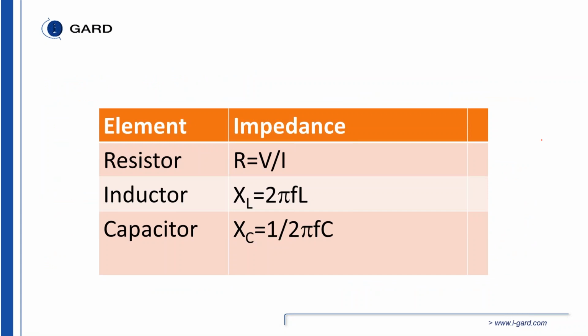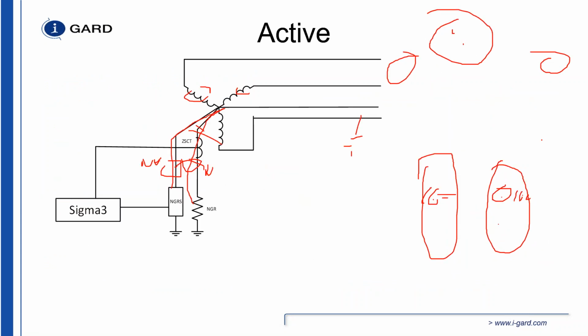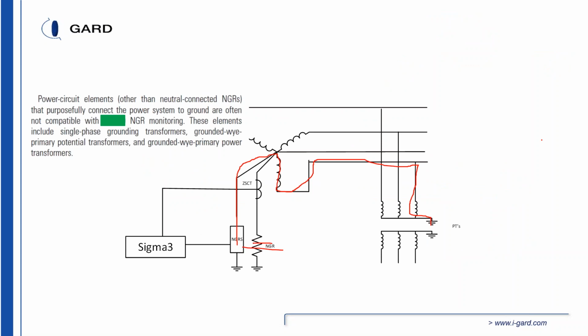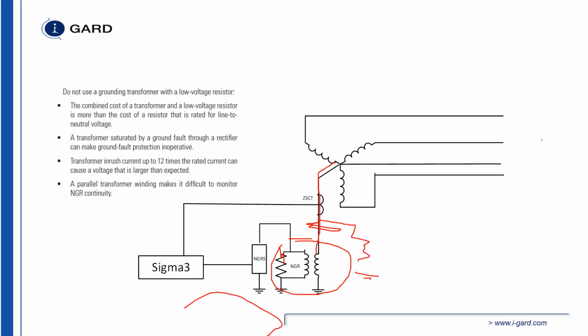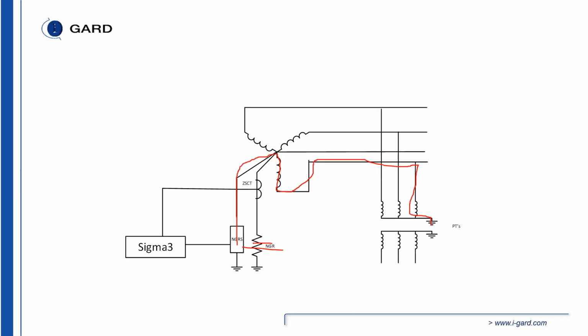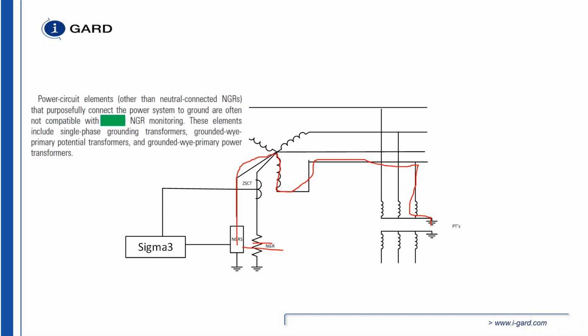Going back to this type of circuit, we are able to detect whether that resistor is going to be open or shorted because we changed the value of the frequency. However, you still have the problem of determining whether the conductor going to the XO bushing is going to be open or shorted. So these types of systems are going to require more engineering on your part because, to comply with the code, you need to monitor the integrity of this cable as well as the resistor. YYPTs are not an issue anymore, not with our device.